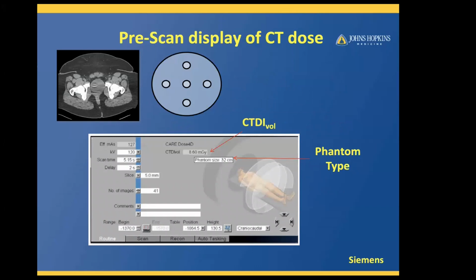Shown here is the display of the CTDI even before the scans are done. This is called a pre-scan display of the CT dose. As you can see here, where the technologists are setting up the technique, the scanners are now required to report the CTDI volume value, and most scanners also tell which particular phantom it is based on, because the manufacturers have built-in tables for all these different kV settings and conversion factors. So automatically, if you change any one of the parameters, this will be reflected here.